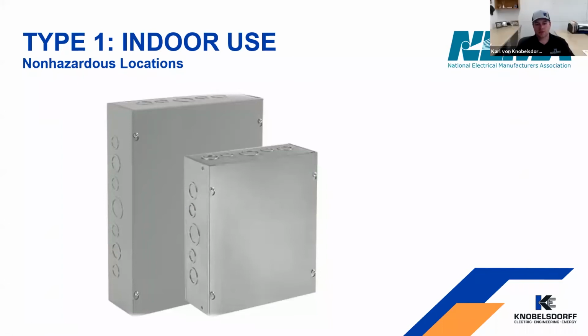So on the screen now we've got enclosures. This is just a regular set screw type box, which is Type 1 indoor use. So this can be used in your warehouses, office spaces, anywhere that's an unclassified non-hazardous location. These come in both painted steel and carbon steel.